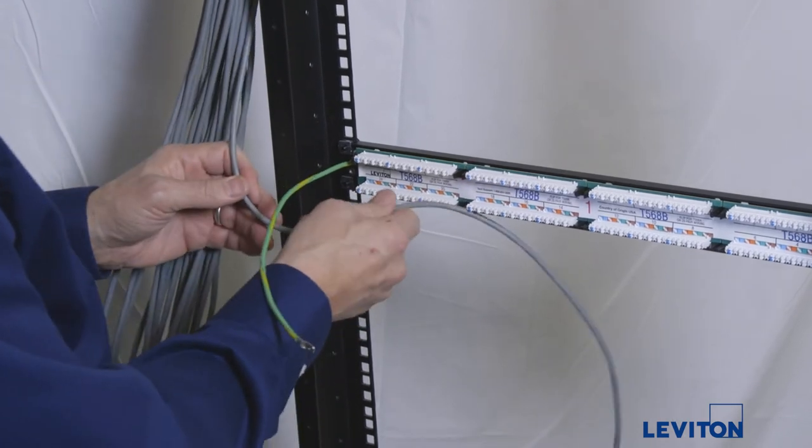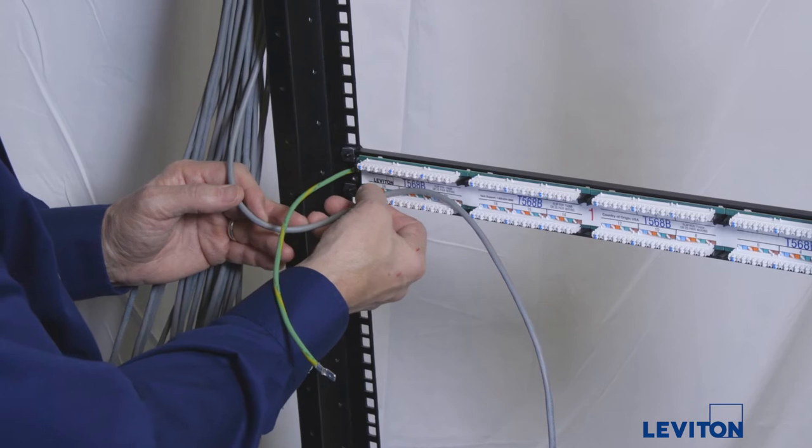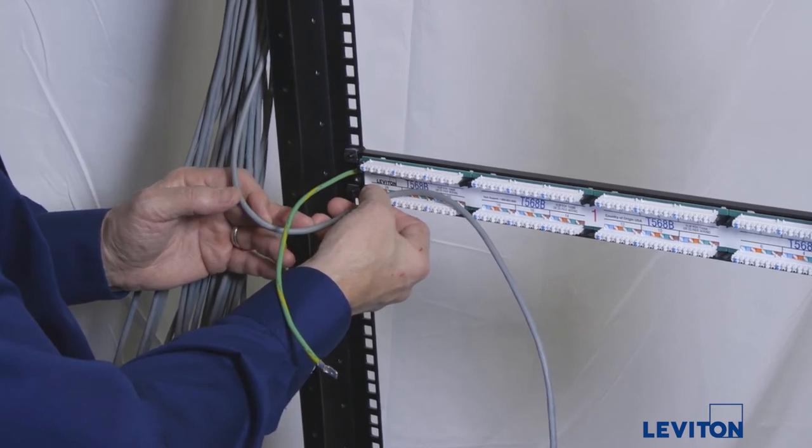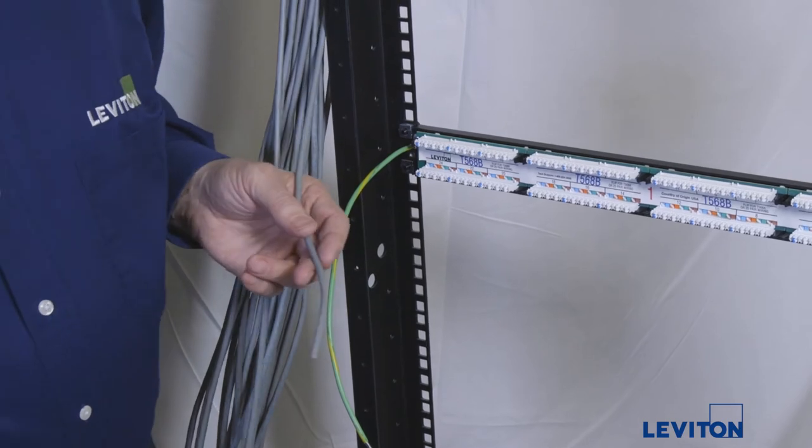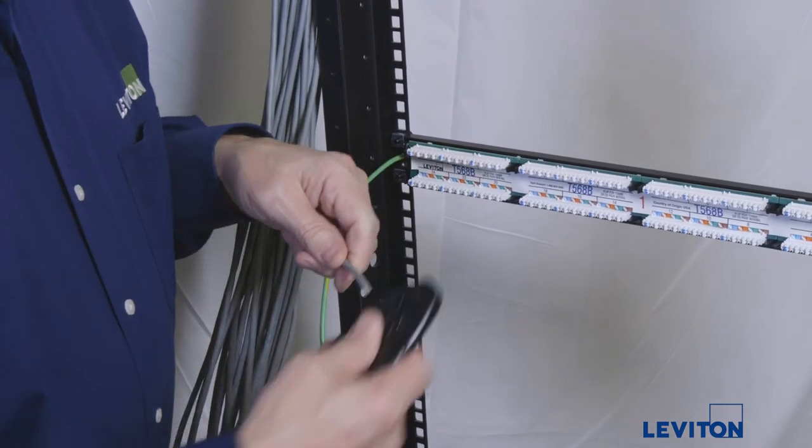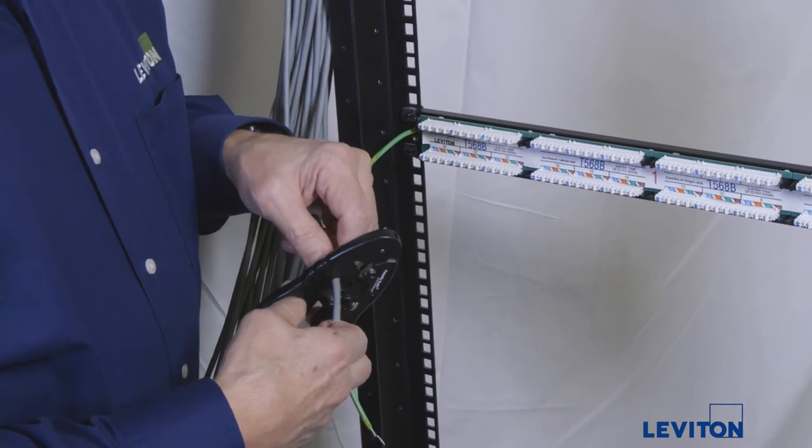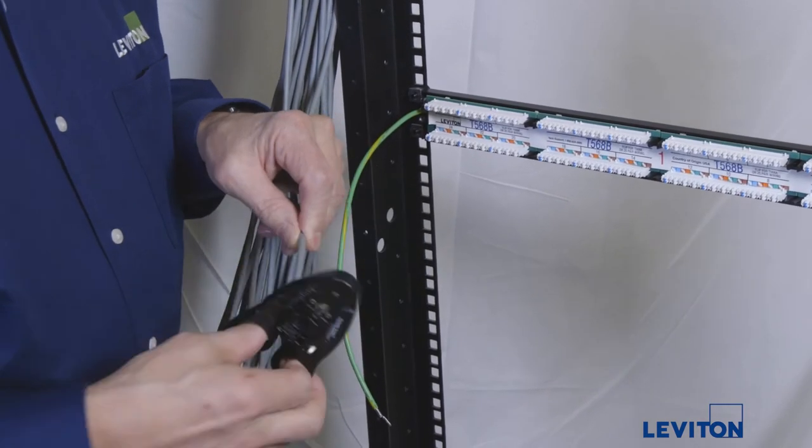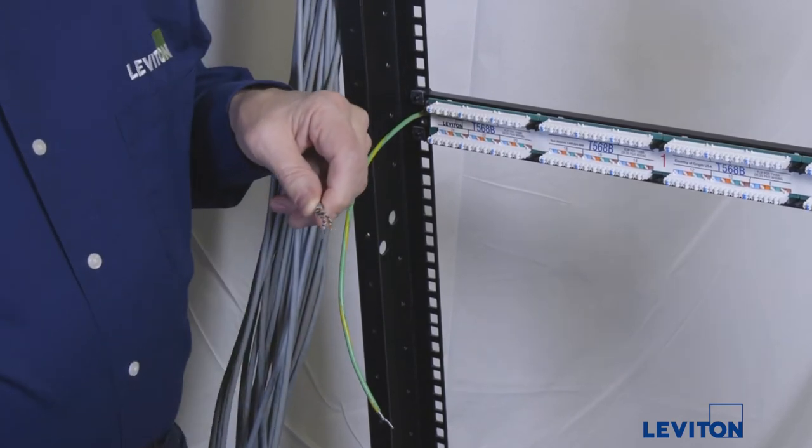Find the cable labeled 24 and measure the length needed to reach from the cable bundle to the patch panel. Mark it with your finger. Take the data wire strip tool and make a cut in the cable using a single circular motion about two inches beyond the point you marked with your finger. Be careful not to nick the conductors. Break the cable jacket and slide it off.